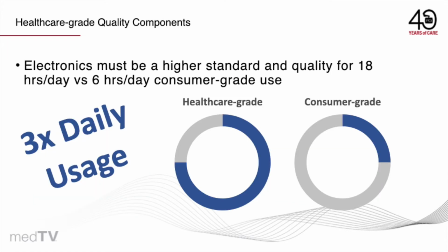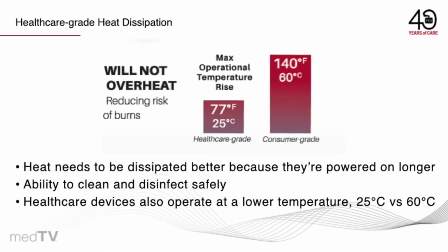Internally, all the electrical components are at a higher standard, typically because of the time that they're on. A residential television set is typically on less than 6 hours a day. In a healthcare environment, our testing shows that it's 18 hours a day. It's a great distraction to the patients. The nurses love it. They leave it on almost all the time. With that longevity or time on comes heat. Heat is the killer, or the bane, of all electrical components. So we dissipate the heat better than in a consumer grade set, while at the same time having to make sure that it can be cleaned, wiped, and disinfected with either a spray bottle or a wet disinfectant rag. We operate our televisions at a lower temperature than a consumer grade product. Typically a consumer grade product has an operating temperature around 60 degrees Celsius. We operate down in the 25 degrees Celsius range.